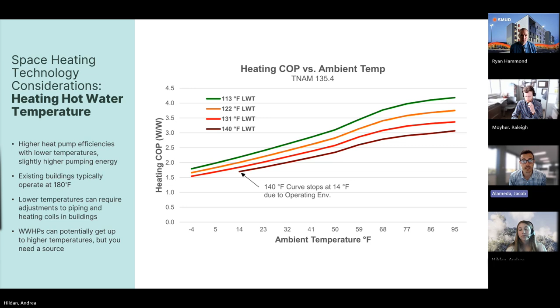So a good first step that we've been recommending to owners is to see if their building can handle lower temperatures. Reset the supply temperature of your heating hot water in the winter and see how low you can go before your rooms can't maintain their set point anymore. Maybe you'll find that only a few zones have issues, and you can limit your coil replacements to just those specific zones. However, there are obviously projects where these temperatures won't work without resizing your building's heating water piping and replacing heating coils. There is some hope that CO2 heat pumps or other heat pump advancements will become available that give you higher supply temperatures from air-to-water heat pumps, but they're not that common at this point.